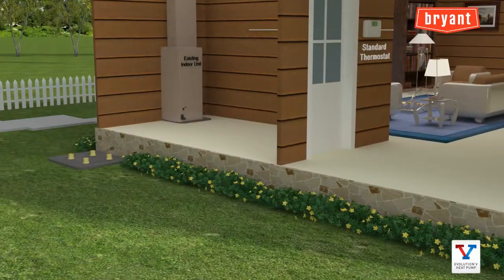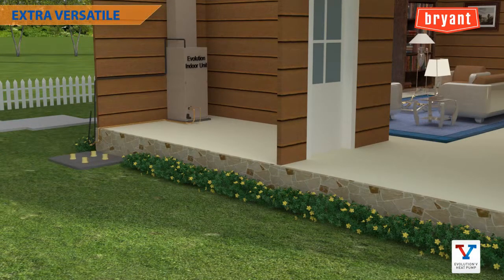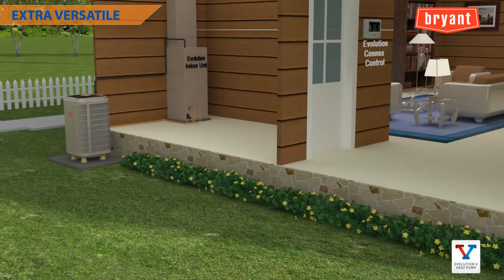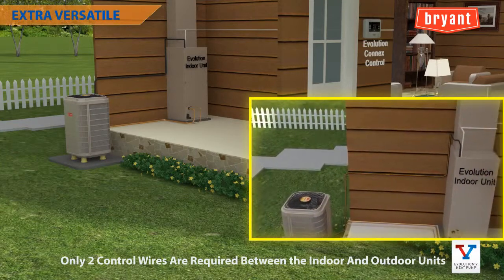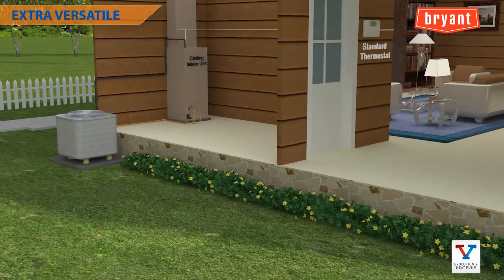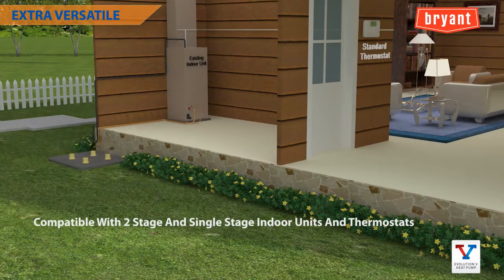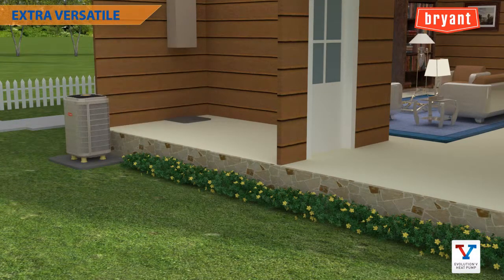This is proving to be one of the most versatile heat pump systems available. When installed as part of a complete Evolution system including an Evolution Connex Control, only two control wires are required between the indoor and outdoor units, making retrofit installations quicker and easier. The Evolution V is also compatible with two-stage and single-stage indoor units and thermostats, allowing dealers to tap into the replacement market with a phased approach — replace the outdoor unit now for partial functionality, then replace indoor components later for full system functionality.